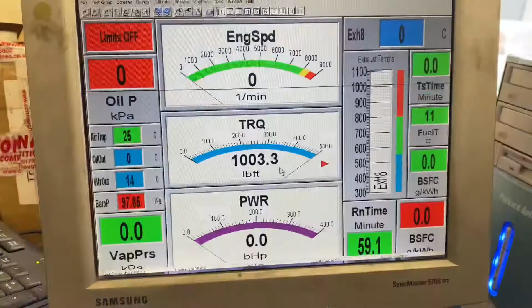Calibration - as I said earlier, we fitted a new load cell and I started to calibrate all the electronics and the voltages, and all appeared to be good until I came in here and tried to hang some weight on it. In theory, it's simple to calibrate one of these, and I'll talk you through what's supposed to happen.